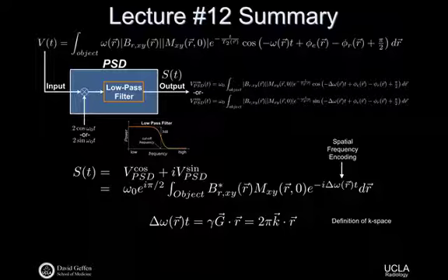So we saw some k-space definitions earlier. There were slightly different forms for the same thing. But we can say that our k-vector, what location we have in k-space, it's a two-dimensional space, so we can think of it as a vector. That's just equal to, say, gamma times the gradient strength times time. Different ways to express that if we want to. We can say it's also 2 pi times your k-vector, gamma times G times time. So it depends on the amplitude and the duration of the applied gradient. It tells you about where you're going to end up in k-space, or what k-point we're actually talking about after some period of time has elapsed.